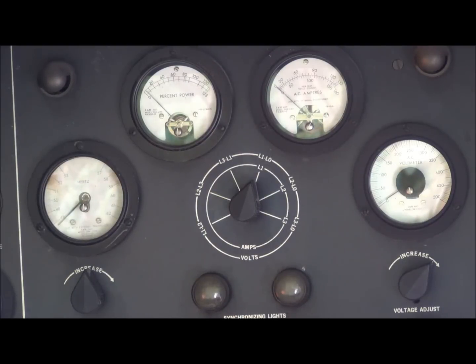Alright, everything seems to be operating properly. As you saw in the video, the generator was able to handle a fairly significant overload without too much droop. I didn't get any spurious trips or anything like that. I went ahead and walked around the generator while it was running under an overload like that. I didn't notice any components that appeared to be getting hot or any melted insulation or anything like that. So now that we've placed this generator under a load, I'm going to test the overload trips on the individual phases.